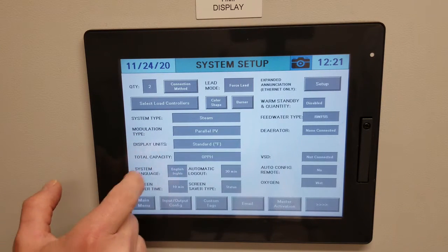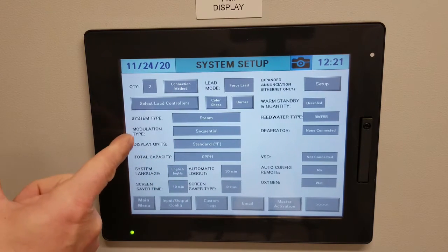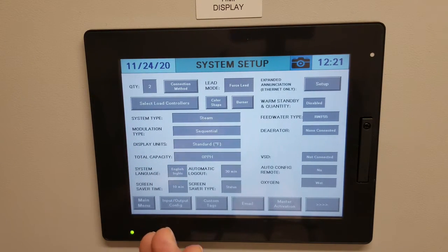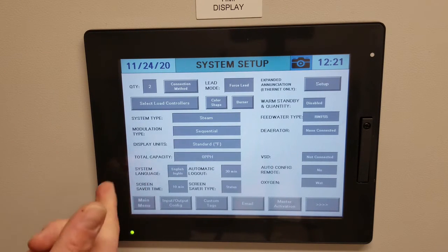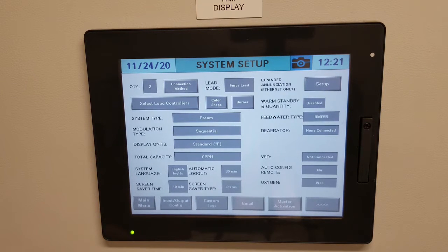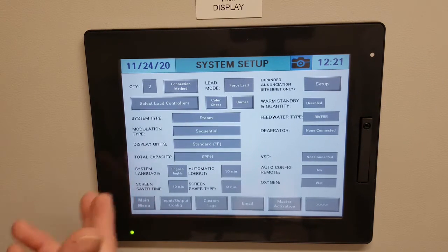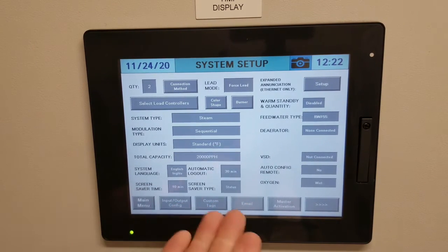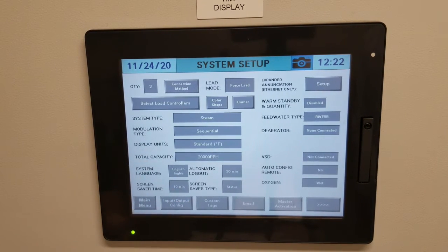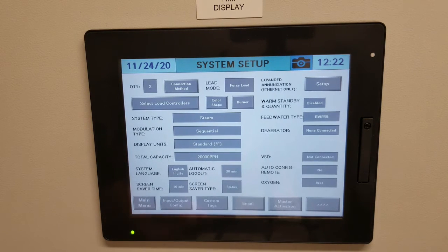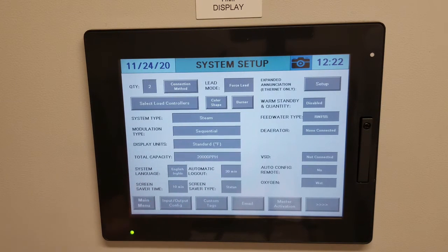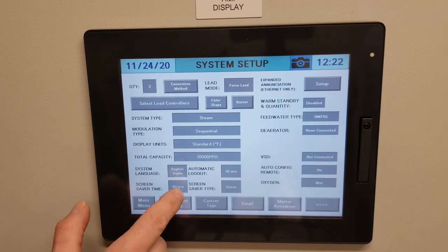Modulation type — you have options between sequential, parallel process value, or parallel. For a lot of steam applications, I use sequential. Display units is degrees Fahrenheit. Total capacity refers to the total capacity of your boilers. If you have two boilers at 10,000 pounds per hour, that's 20,000 pounds per hour total. System language is English. Automatic logout means if you walk away and forget to log out, after 30 minutes of inactivity it will log you out automatically. You also have a screen saver set for 10 minutes, and you can select status or blank as the screen saver type.